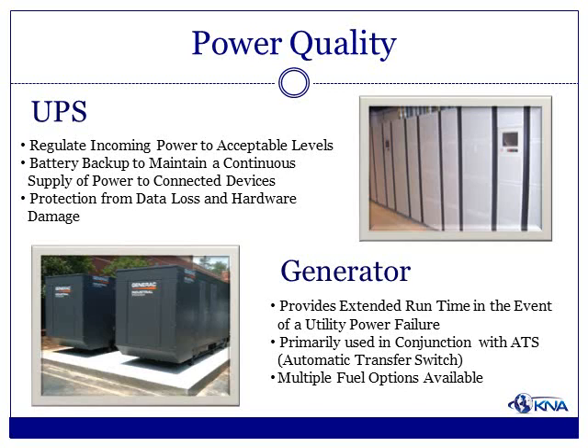Many times equipment other than the UPS needs to remain operational when utility power fails. Whether the requirement is for emergency or standby power, KNA provides and installs commercial or industrial-grade generator sets. Typically, an automatic transfer switch is used with the generator to provide seamless transition to utility power or generator power. KNA is able to provide generators from various manufacturers as well as in multiple fuel types, which provides flexibility when properly designing a backup power system.